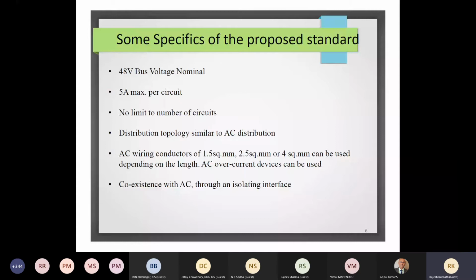So here you'll have a DC distribution box, and you will have multiple circuits, and each of these circuits will have a 5 ampere current limit. So in the initial standard, we have not really limited the number of circuits, but there could be some limitation coming in future, because the feeder line might need some current restriction, etc.